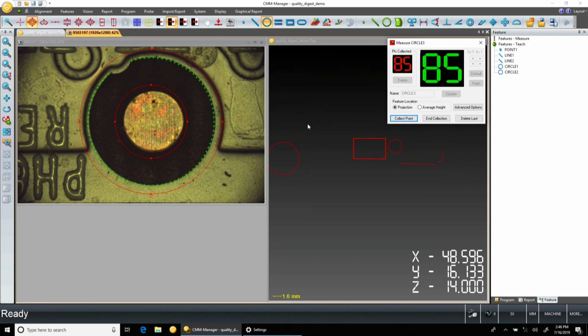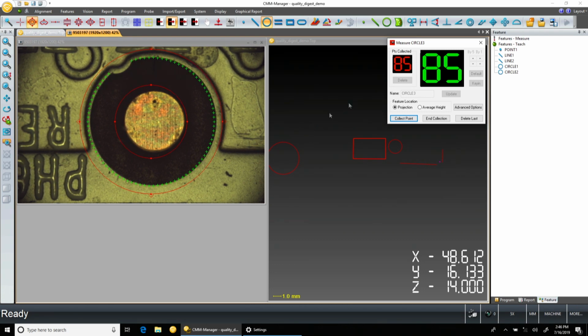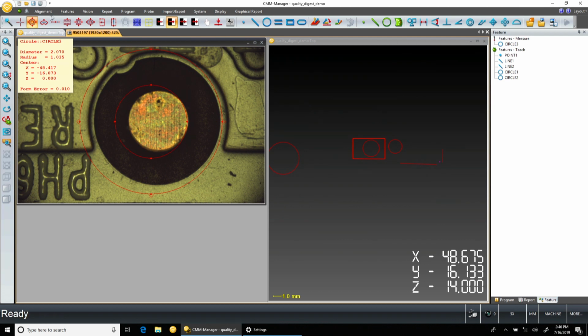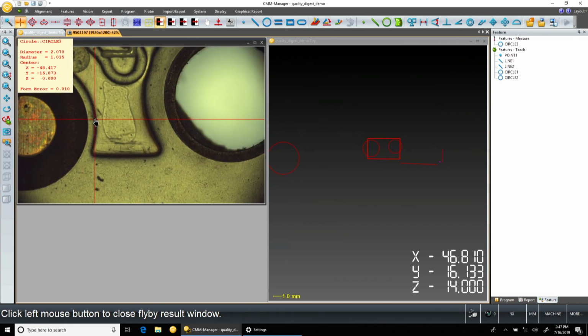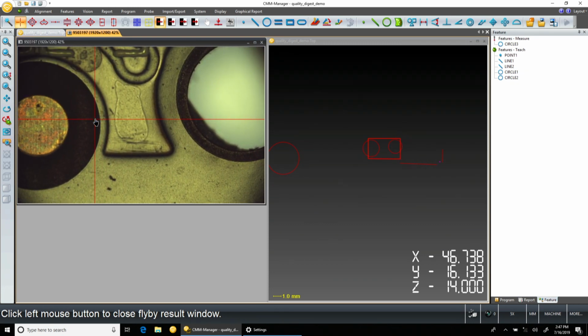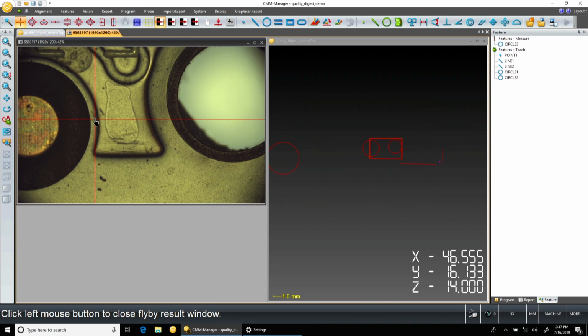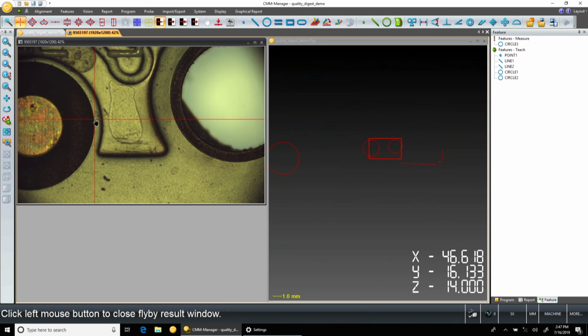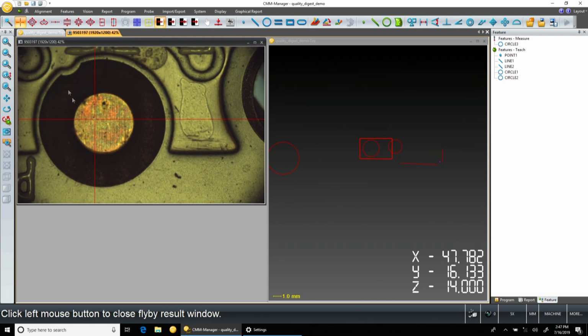And we find all of those edges automatically. In contrast to the traditional way that you might do that, using a crosshair and even looking through the optics on the microscope, manually moving a crosshair or manually moving the stage to register that crosshair can be very subjective, and you may get different results from one operator to another, where using edge detection gives a lot more repeatable and accurate results.